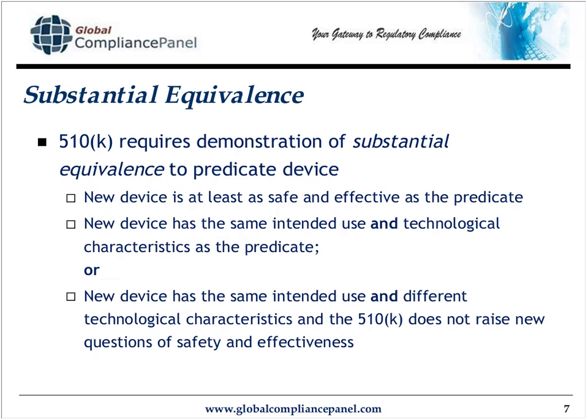The concept of substantial equivalence is not identicalness. It's equivalent. It's substantially equivalent, so it's a little more than just equivalent. And what you're saying is that your device is at least as safe and effective as the predicate. The way to normally do this is to provide safety and efficacy data with your submission.